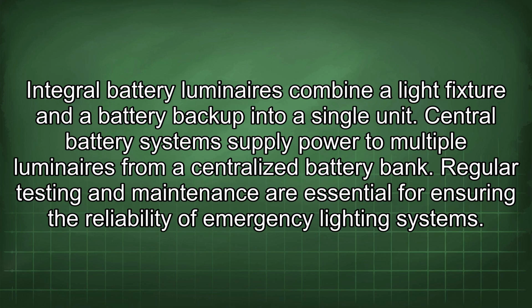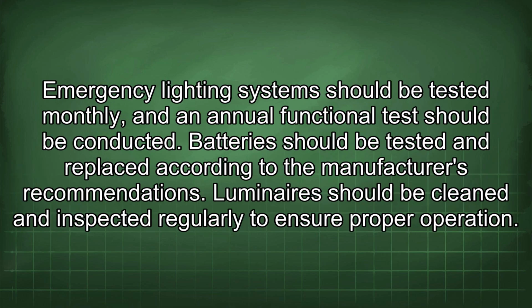Regular testing and maintenance are essential for ensuring the reliability of emergency lighting systems. Emergency lighting systems should be tested monthly, and an annual functional test should be conducted. Batteries should be tested and replaced according to the manufacturer's recommendations. Luminaires should be cleaned and inspected regularly to ensure proper operation.